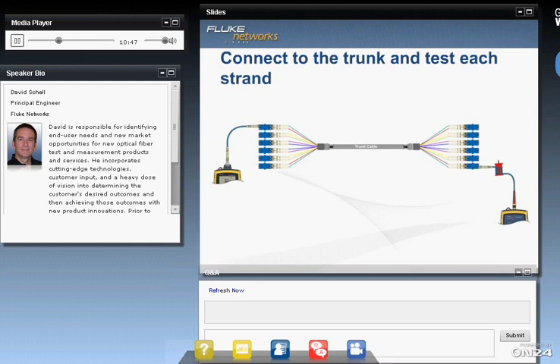We connect our light source to one end, usually fiber 1, and then connect the power meter to the fiber from which the source light will exit. That might be fiber 1 if it's Type A, fiber 12 if it's Type B, or fiber 2 if it's Type C — so you have to know the polarity and where to find the output. Then you step-by-step test each of the 12 fibers, measure it, record it, make sure you've recorded the correct location, and going through all 12 takes quite a while.